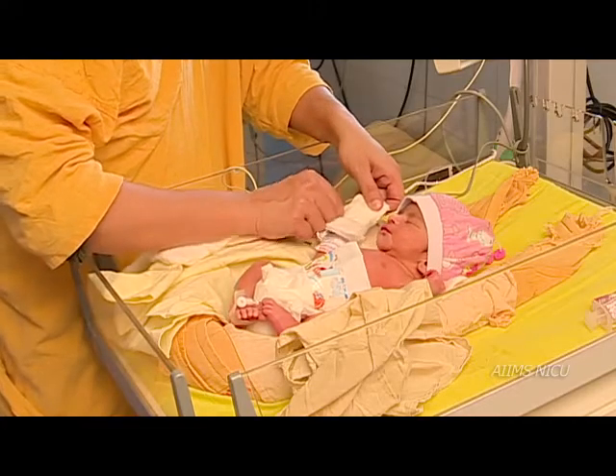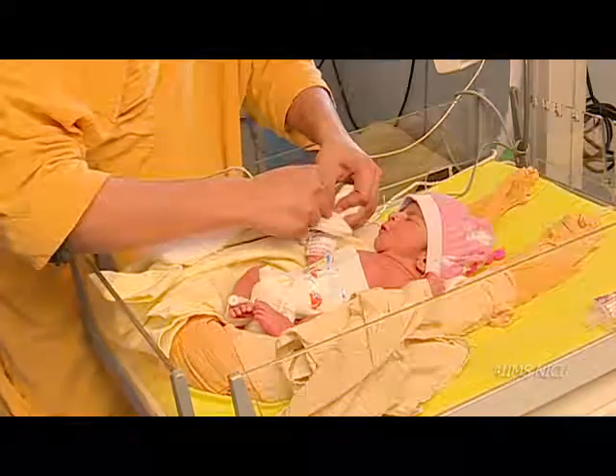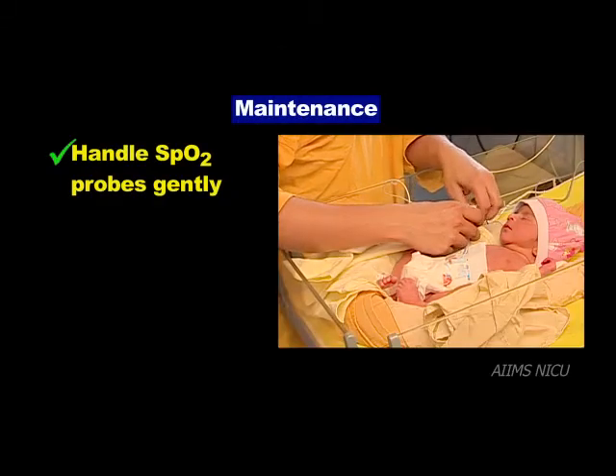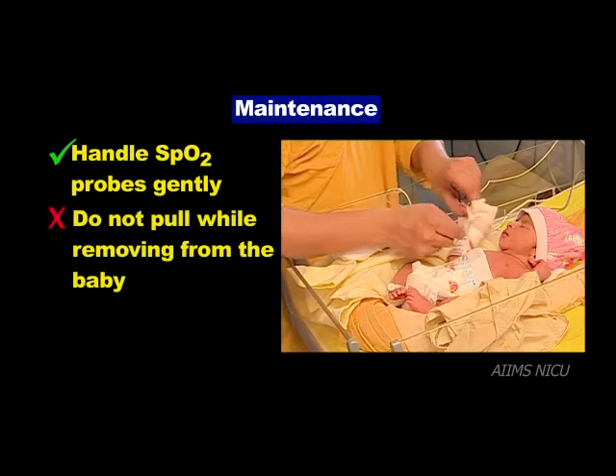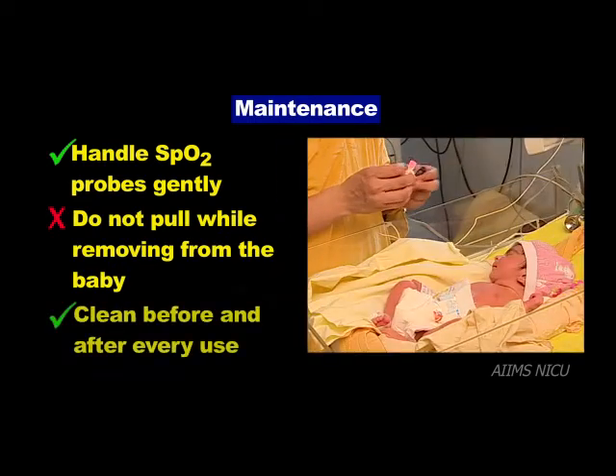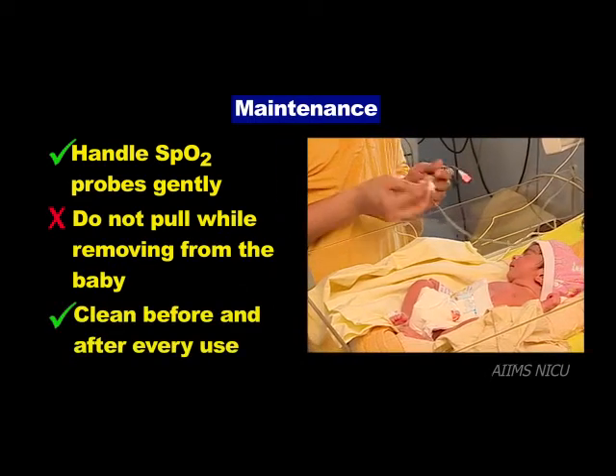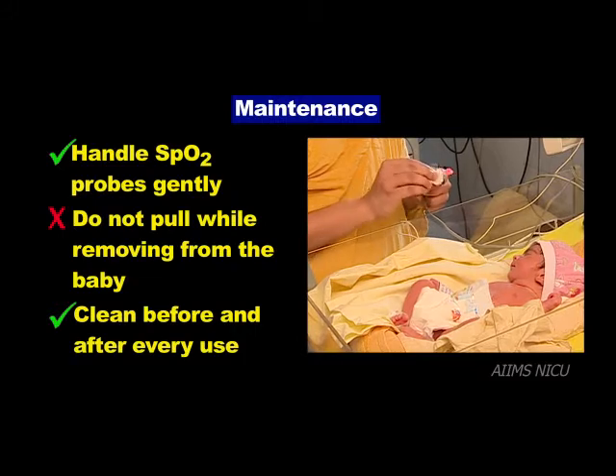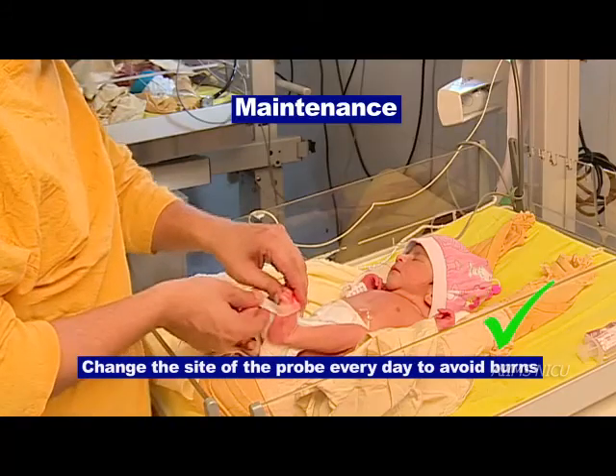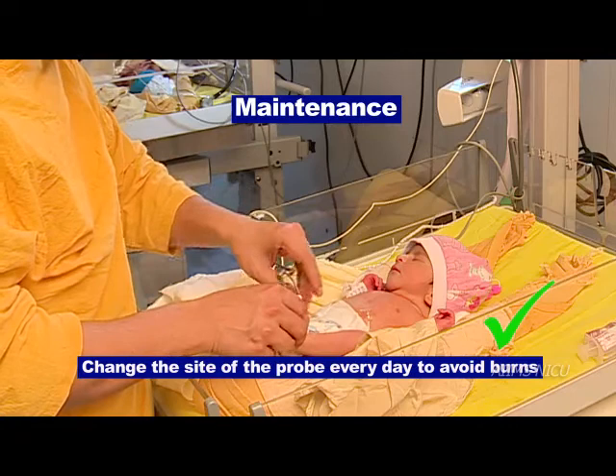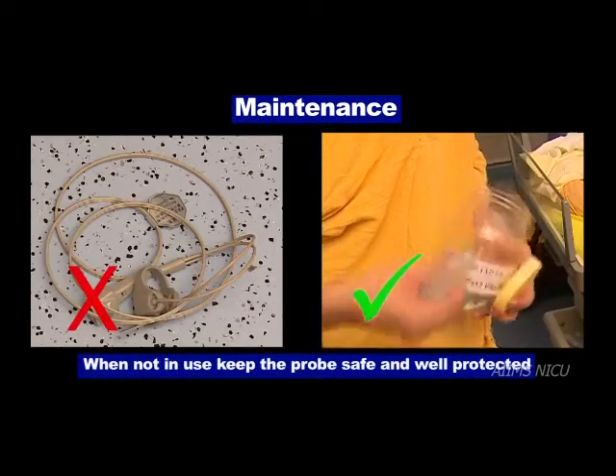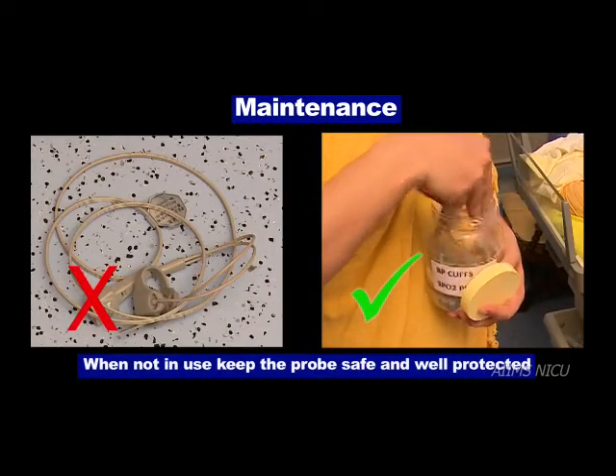Some important points to be noted for maintenance. Handle the SpO2 probes gently. Do not pull while removing from the baby. Clean before and after every use. Change the site of the probe every day to avoid burns. When not in use, keep the probe safe and well protected.